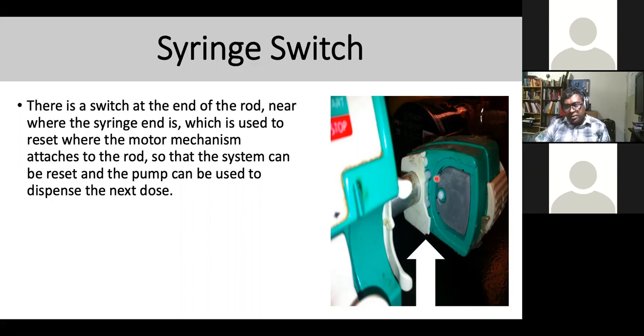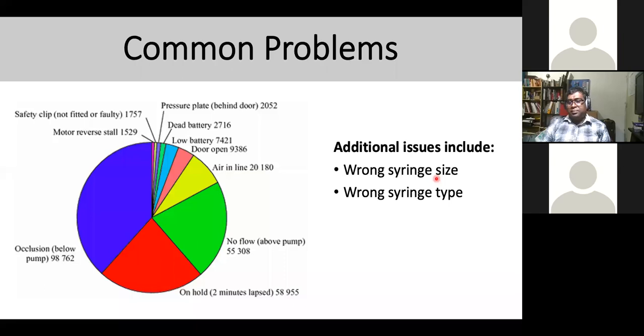And you can see that's a broken part of it. The white one is a clip, and it's broken. This is a very common thing that you're going to see in the syringe switch part. It breaks because of rough use, all this. Common problems you're going to see: wrong syringe size, wrong syringe type, occlusion issue, pressure plate, dead battery, low battery, door open issue, air in line, no flow, safety clip broken, and the motor not working properly, or reverse, or stall. So these are common problems that you're going to see.